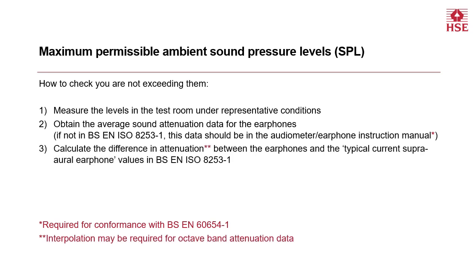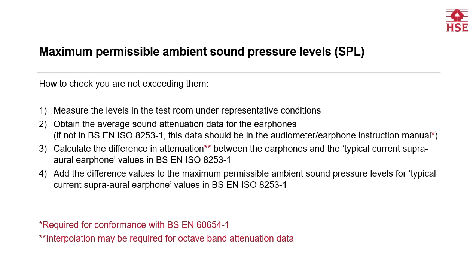3. Calculate the difference in attenuation between the earphones and the typical current supraoral earphone values in the standard. 4. Add the difference values to the maximum permissible ambient sound pressure levels for typical current supraoral earphone values in the standard. And 5. Compare the result with the levels measured for the test room.